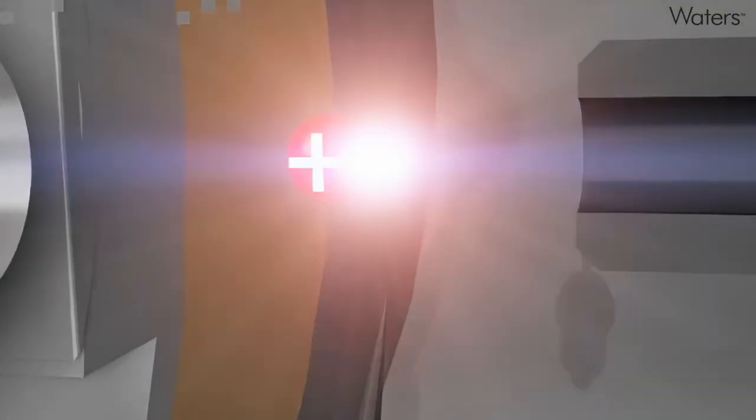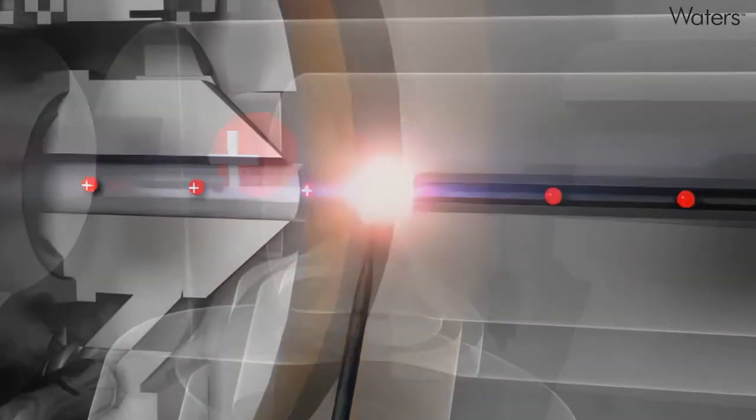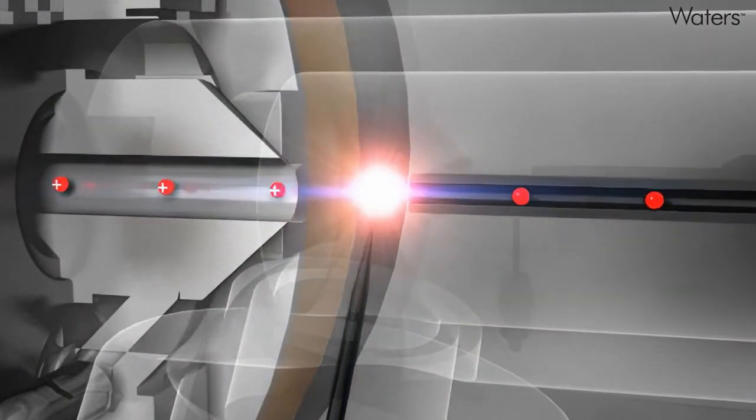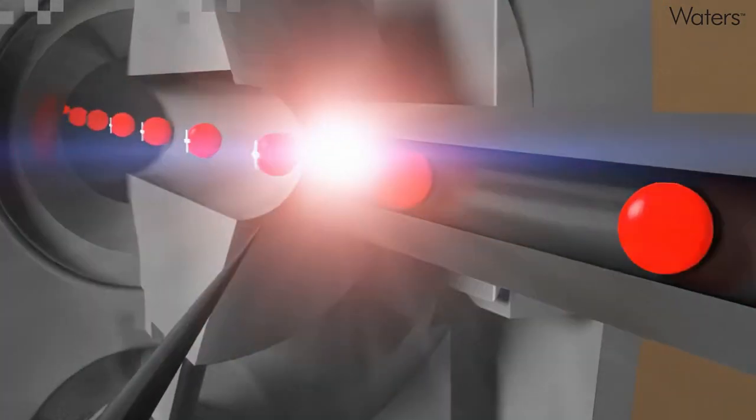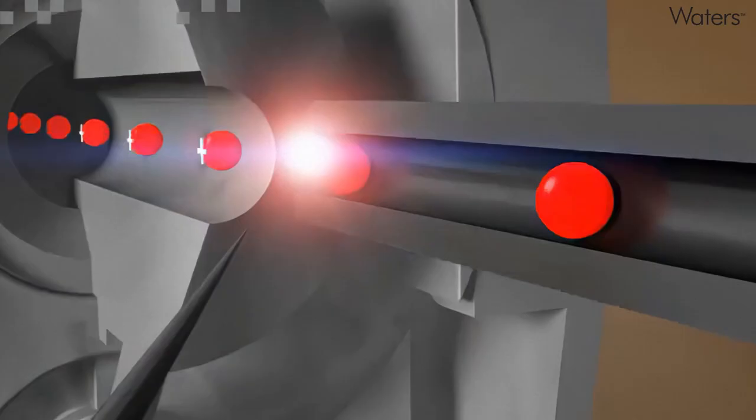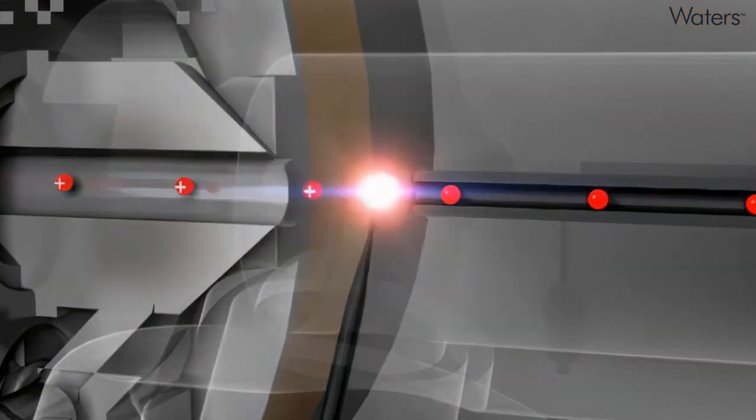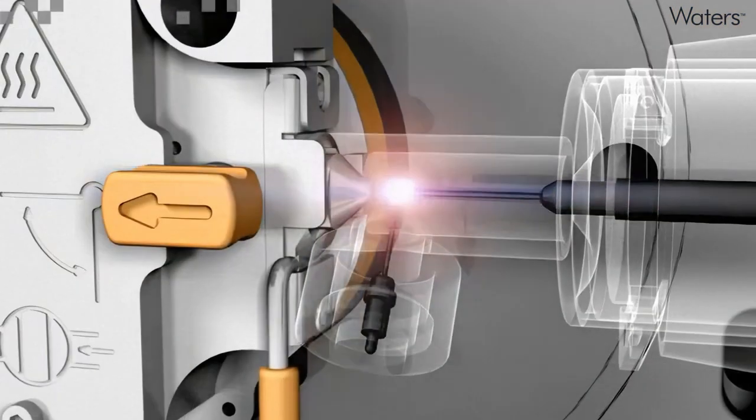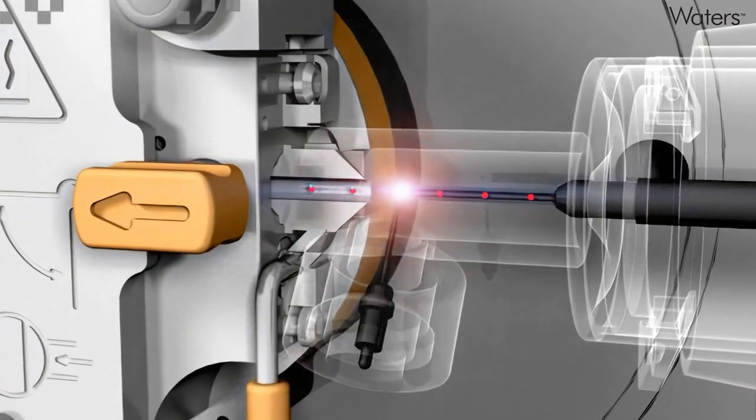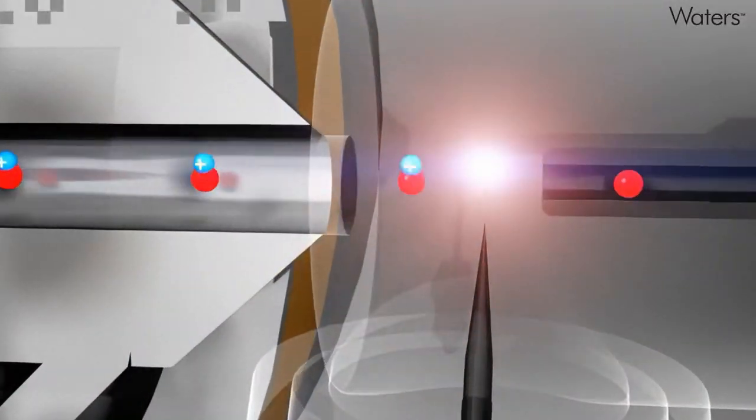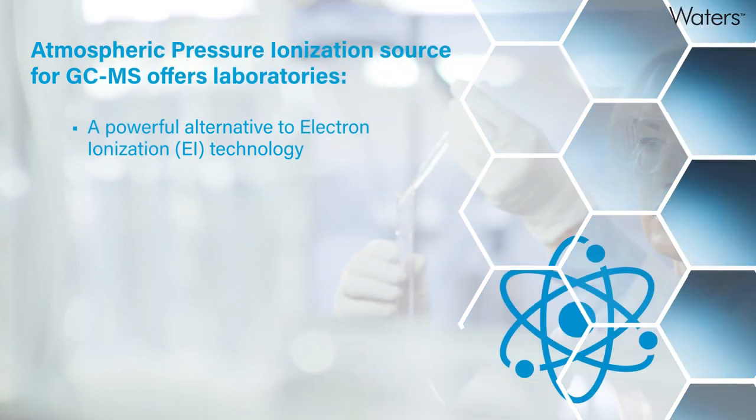APGC ionization is soft, which minimizes compound fragmentation, and results in an enhanced abundance of molecular ions compared to electron ionization. Ionization can be controlled in favor of charge transfer, which generates M-plus ions, or with addition of reagents such as water or methanol, protonation to M-plus H.